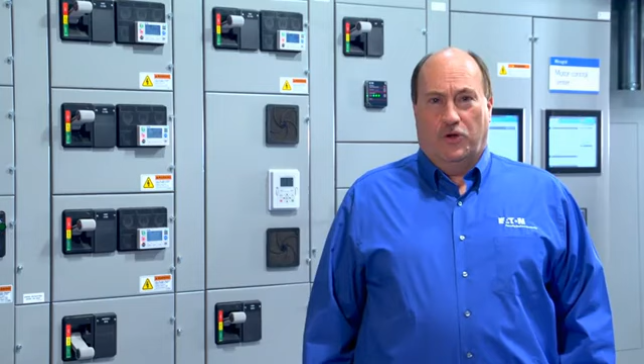For certain utility disturbances, or when islanding is initiated manually, it is possible to transition from grid-connected to islanded states with no power disruption, referred to as seamless islanding. This process includes adjusting the output of the energy storage and the generator to match the load, shedding some microgrid load if necessary, then disconnecting from the utility.